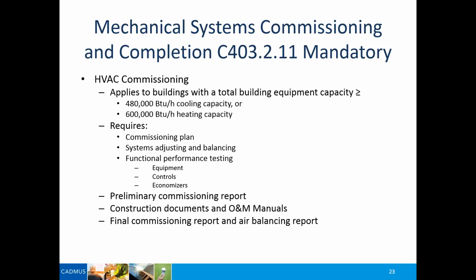Now, a lot of times the final commissioning isn't done until after certificate of occupancy. There's a lot of discussion in the code about how this should work, because from a jurisdictional standpoint, most jurisdictions do not want to hold up C of O because commissioning hasn't been completed. So this final commissioning report can go to the building owner after C of O, just to get the people in the building, but you do need to follow through and make sure that everything is working the way it's supposed to be working.